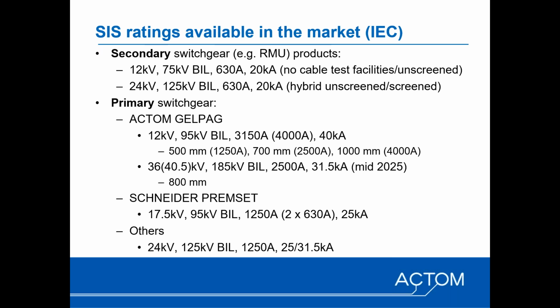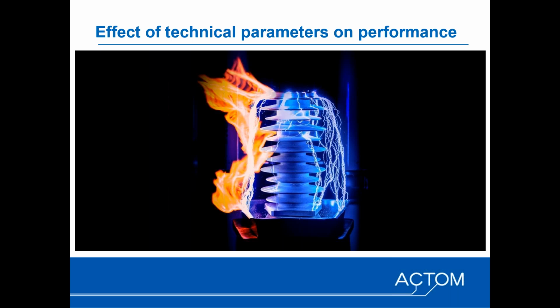And it's great and exciting to point out that we're currently working on a 36 kV, 40.5 kV solution with our partner Gelpag for up to 2,500 amps and 31.5 kA, which will be available from the middle of next year. We're currently busy with the type testing of that solution. That would be 800 millimeters wide. But for the sake of time, I'm now going to hand over to Johan Jordan to take you through some of the more interesting technical parameters on performance.